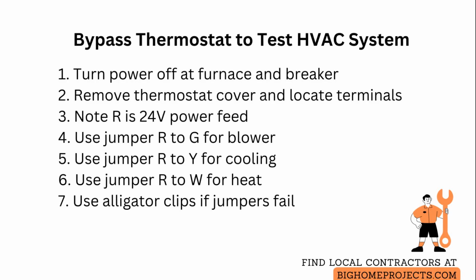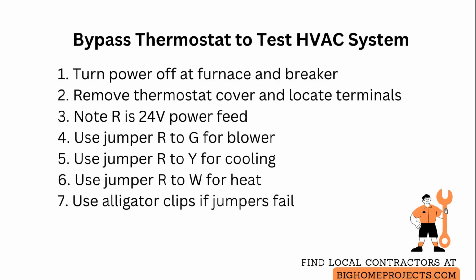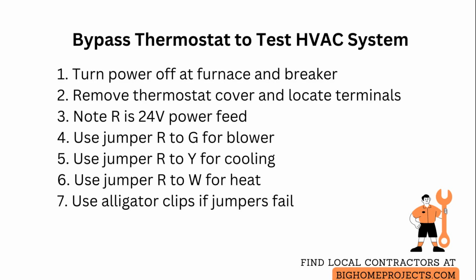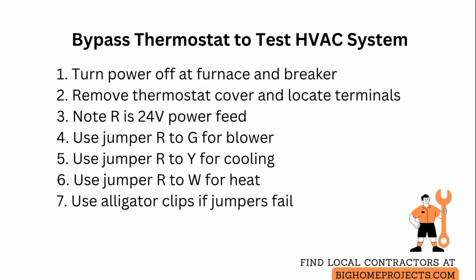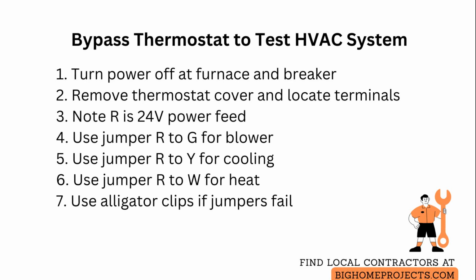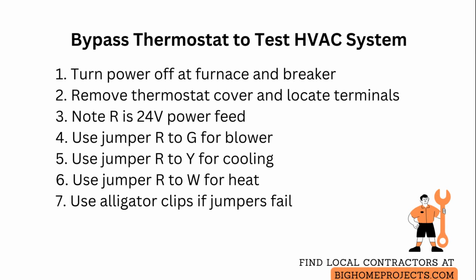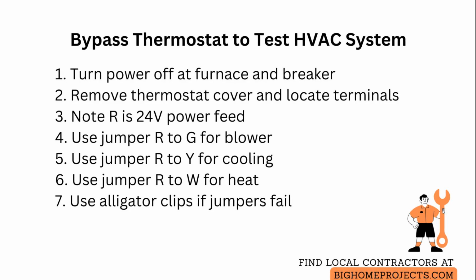Remove the thermostat cover and locate the wire terminals labeled R, G, Y, and W. R is the 24-volt power feed, G controls the fan, Y controls cooling, and W controls heat. If the thermostat uses a battery only for display but the system still has a 24-volt transformer, leave the transformer power off while making connections and then restore power to test.